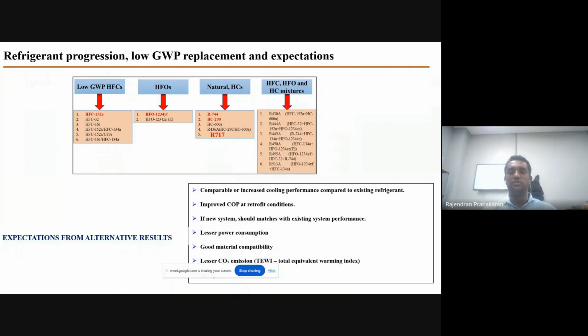Some other refrigerant mixtures are also listed. From all these refrigerant mixtures, the expectation is that they should give comparable or increased cooling performance compared to the existing refrigerant, and also improved COP at retrofitted conditions. Retrofitted condition indicates that there will be no changes at the system component level, only the change of refrigerant from the old one to the new one. And if it is a new system, it should match the overall existing system performance, consume less power, have good material compatibility, and emit less CO2. So these are the real expectations from the various alternative refrigerants.